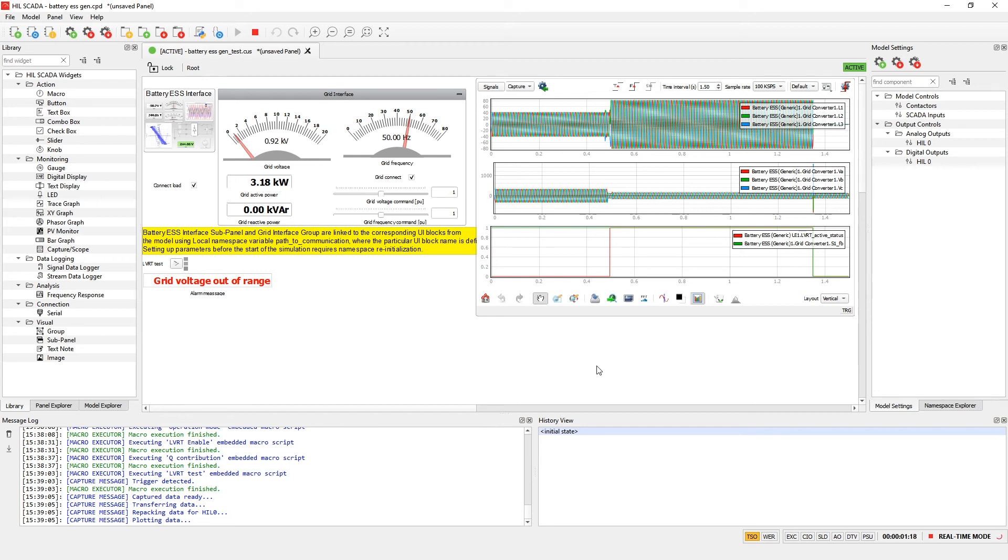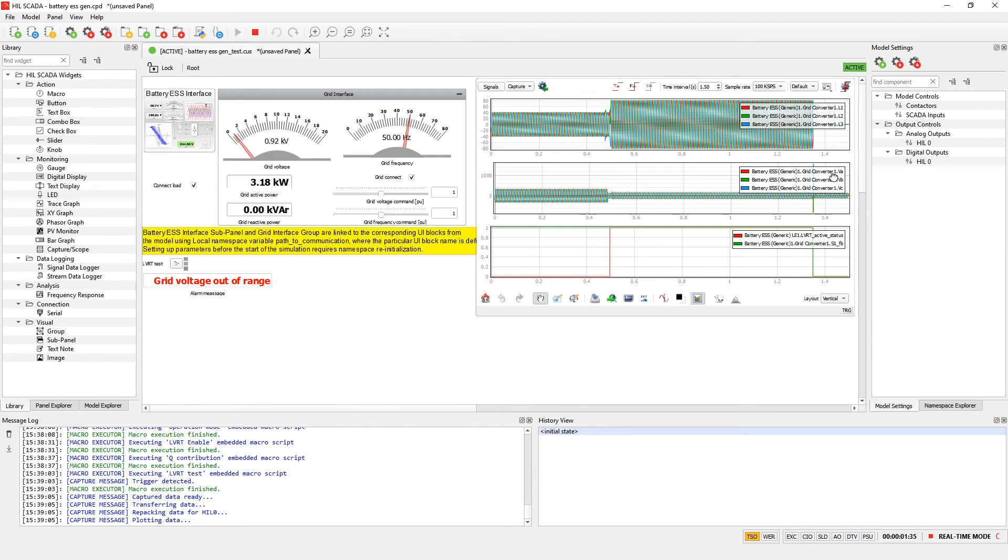Also this test case shows how LVRT works. Here we can see that battery ESS injects active and reactive power during low voltage transitions. This period of time is defined by LVRT requirements. Also injection of the reactive power is defined by the Q contribution slope. After approximately 1 second battery inverter will go off state.